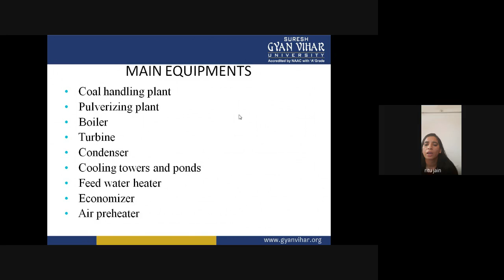Coal is transported to the power station by rail or road, stored in the coal storage plant, and then pulverized. The function of the coal handling plant is automatic feeding of coal to the boiler furnace, because we need a large amount of coal and we can't feed that coal manually. So we need some automatic machines or procedure by which the coal is fed into the boiler or furnace automatically. The coal handling plant gets the coal from other places by rail or road, and then it is stored in the plant.